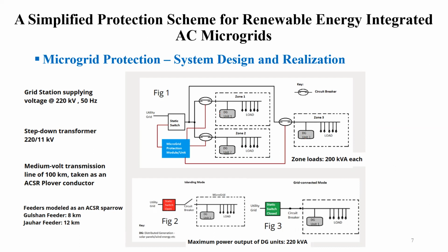Here the system design and realization of our network is shown. We are using the conventional Pakistan grid station supplying 220 kV at 50 hertz. All the transformers are step down transformers, 220 to 11 kilovolts. On the transmission side, we are considering medium transmission voltage lines, and for our simulation we have used ACSR Plover conductors of 100-kilometer length, and these values are taken from NTDC values.